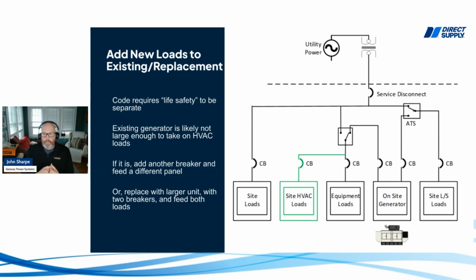The question is going to be, when you do this, is the generator that you have on site large enough to carry those additional loads? Is the transfer switch that is now feeding the equipment and HVAC loads large enough to handle those loads? Is the circuit breaker on the generator large enough to do so? So those are things you're going to have to check out in the assessment: do we have enough power to now back up all these additional loads without having to do a whole lot of work?